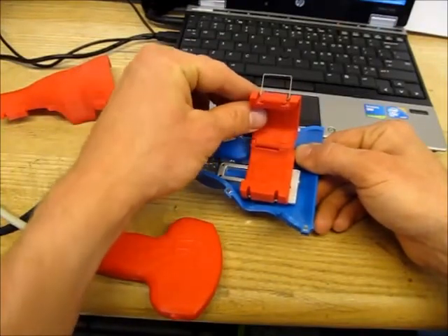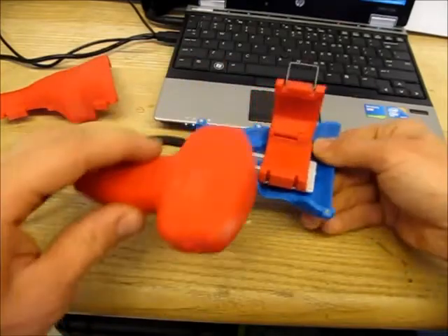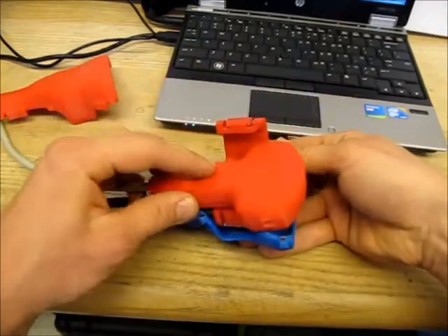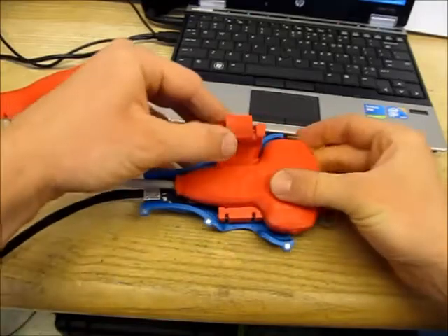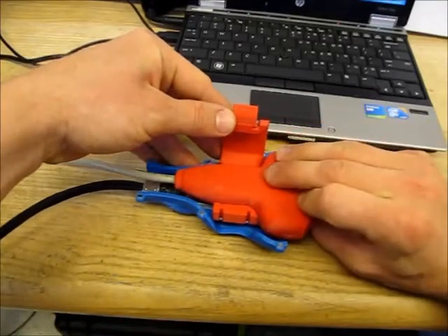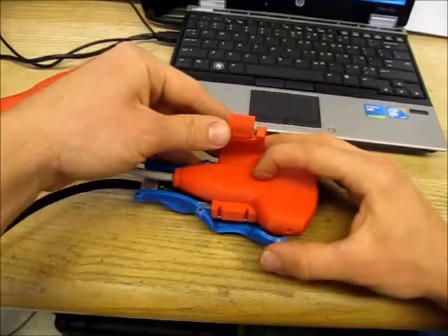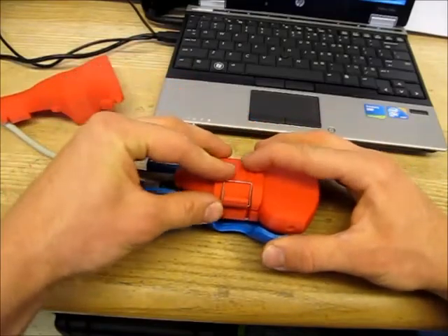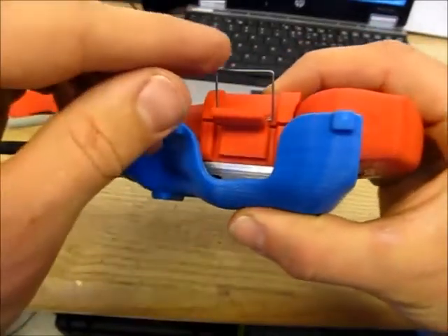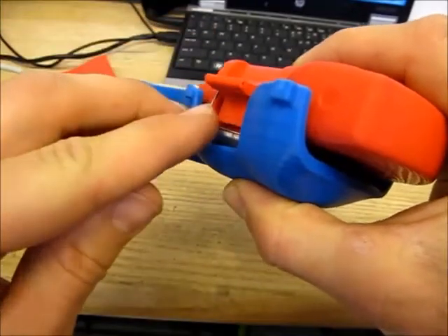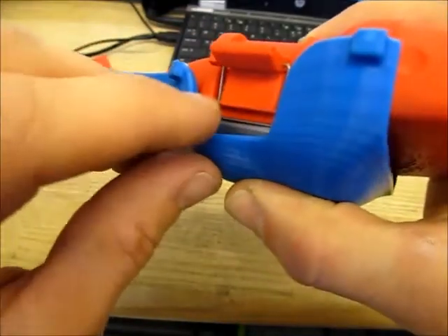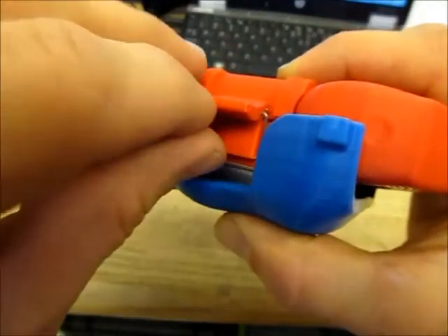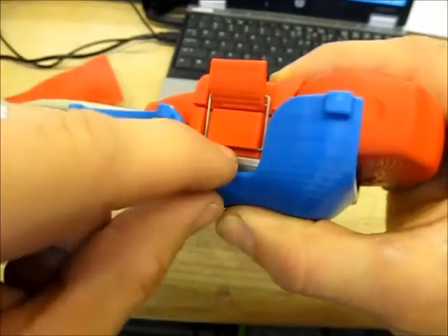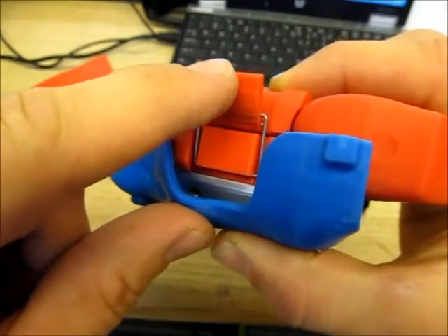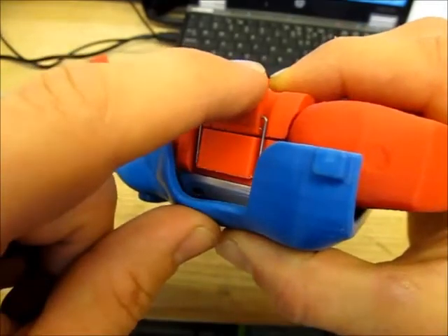So first we pivot the top half of the clamp up. Then we insert the ultrasound probe. Now the ultrasound probe can actually go either this way or that way, doesn't matter. Choose whichever way is convenient. And we bring the top half down and we flip this little metal wire so it goes underneath this lip, the little lip in this plastic piece here. So we pivot it underneath of that lip, and then when it's underneath, then we go ahead and lock this latch here on the top.